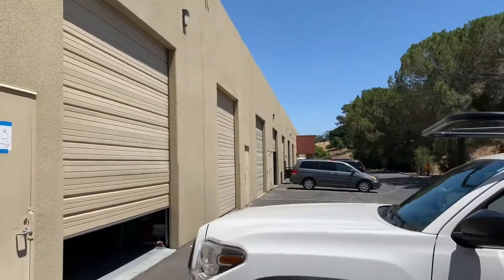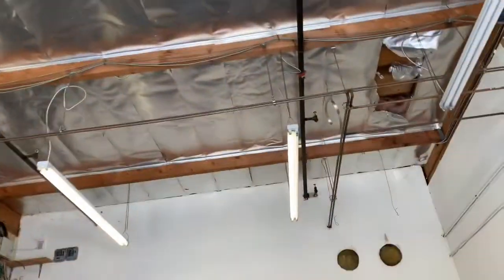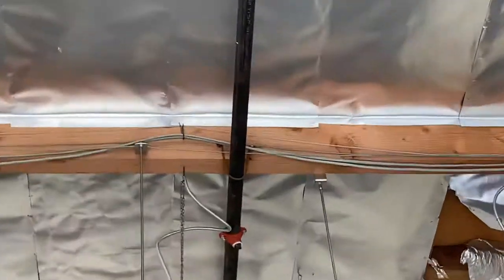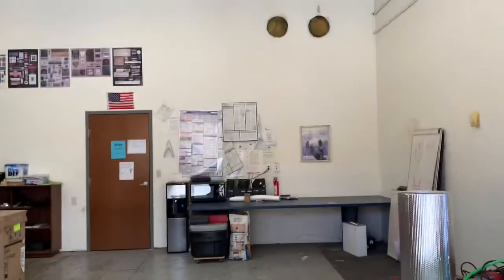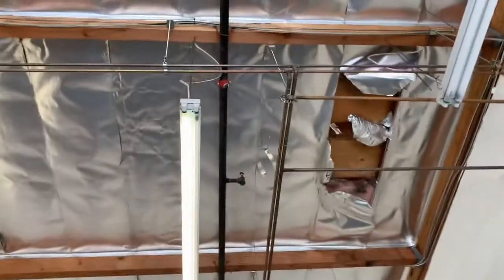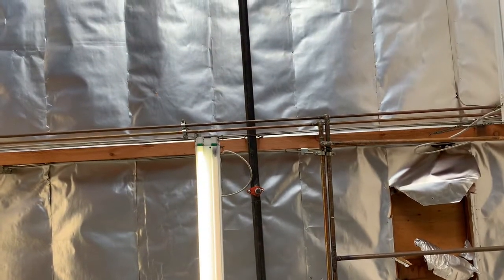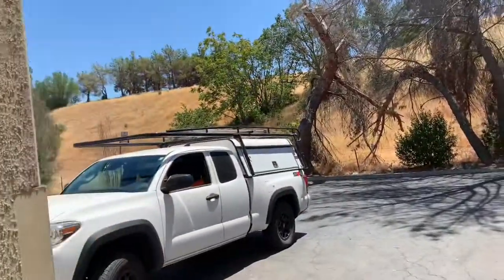The culprit is they're doing work down there on a TI where that bathroom is, and every day they're draining this thing, so it's filling up full of air. At this location, they got a pinhole — that's the one I just fixed. Two-by-one mechanical T with a one-inch plug. I'll walk underneath it because that will always tell you if something is dripping. We see that it is dry, but there is a little bit of water from the pinhole.